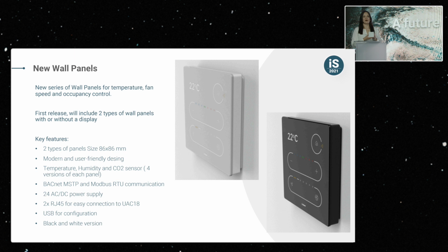The new line of wall panels was designed for temperature, fan speed, and occupancy control. A modern front glass panel hides capacitive buttons for seamless use. The size, 86 by 86 millimeters, perfectly fits a standard electrical box. Wall panels will be available in black and white, with or without a display showing sensor information, and with a choice of 4 configurations of temperature, humidity, and CO2 sensors. You can communicate with the panels using BACnet MSTP or Modbus RTU. For easy and fast connection with the UAC 18, the product will have RJ45, providing both communication and power supply to the panel.